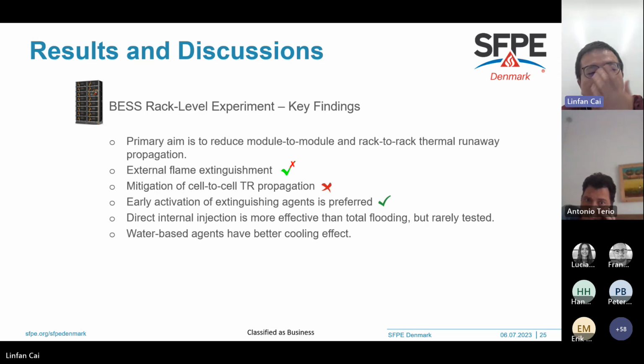Okay, so the key findings for the rack level experiment. In the rack level experiment, the primary aim is to reduce module-to-module or prevent rack-to-rack thermal runaway propagation, but not to mitigate the cell-to-cell thermal runaway propagation, because as shown in the earlier illustration, the cell is within the module box.